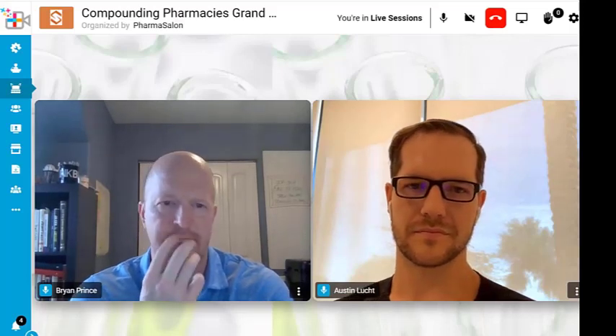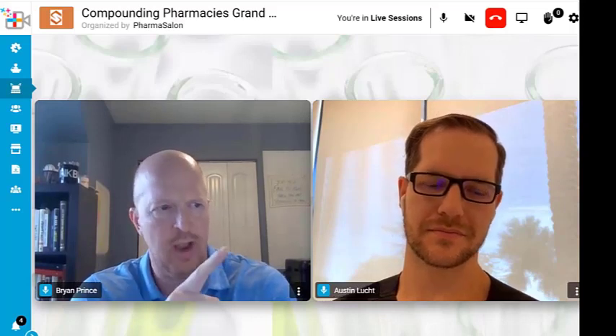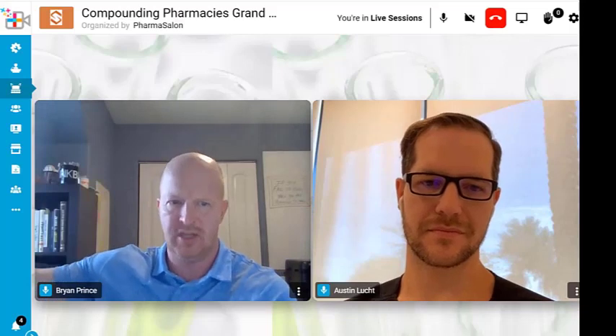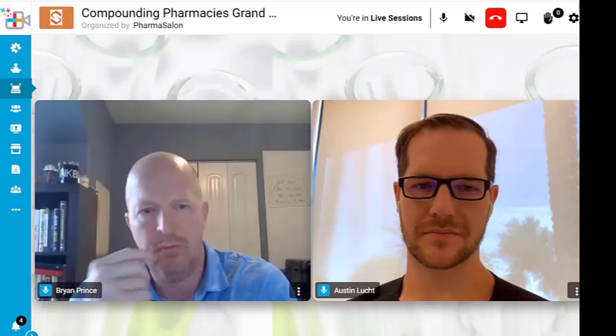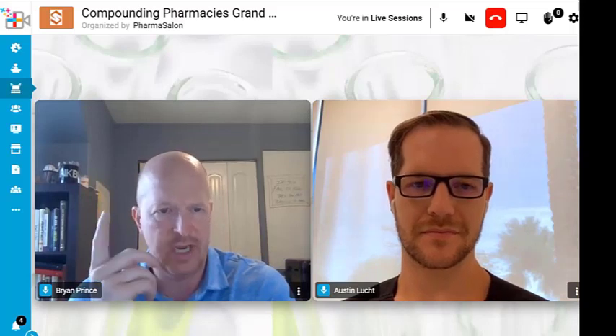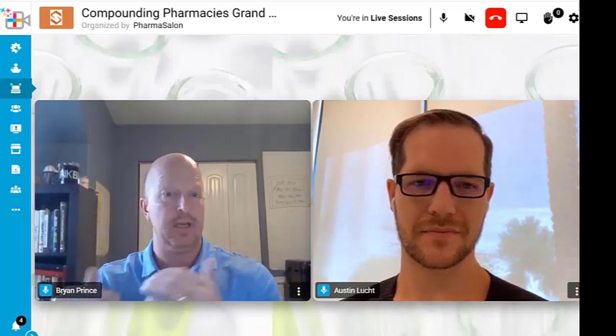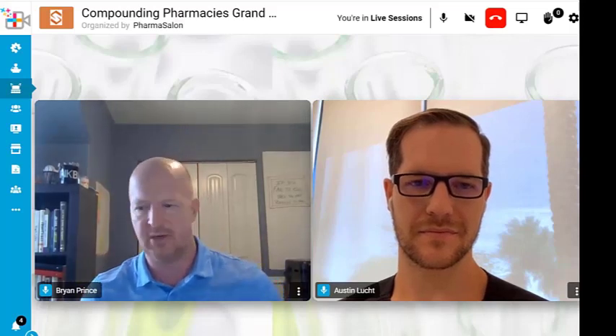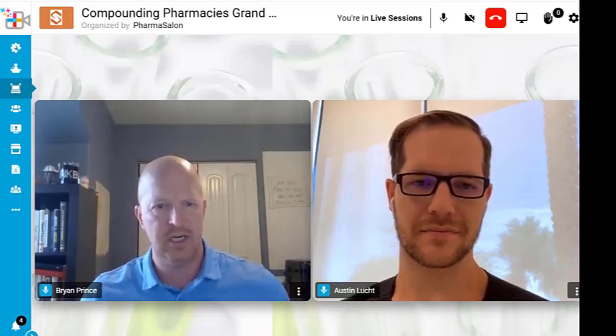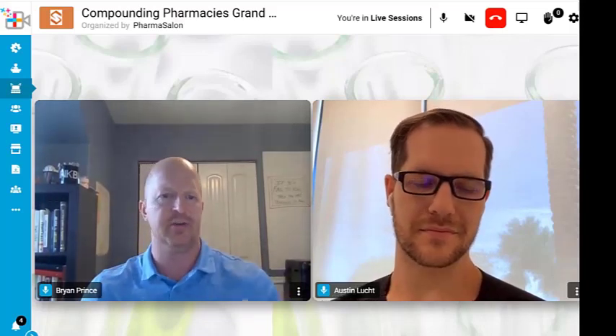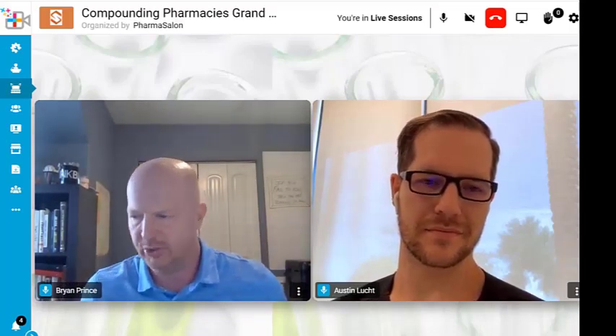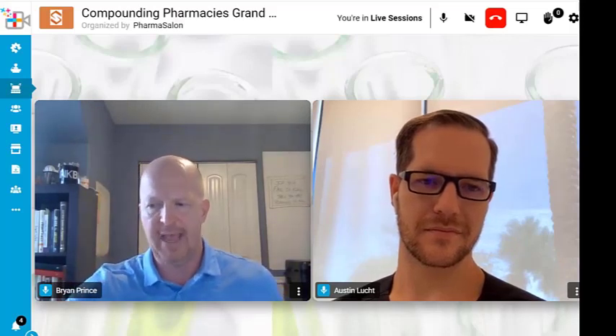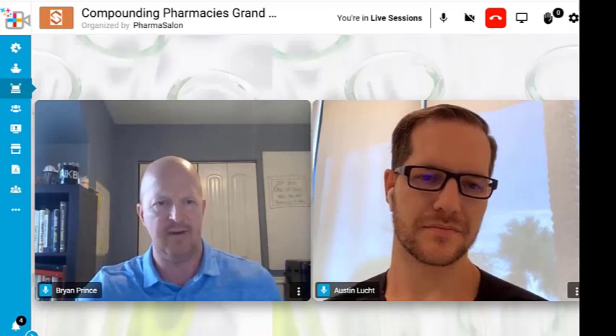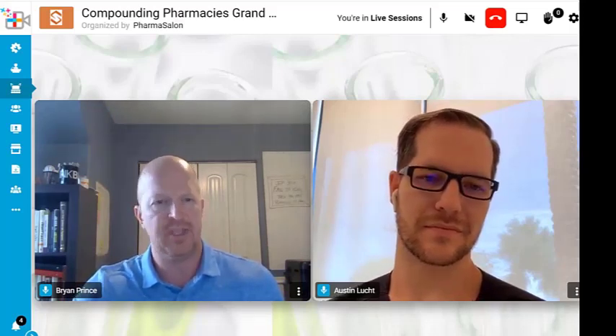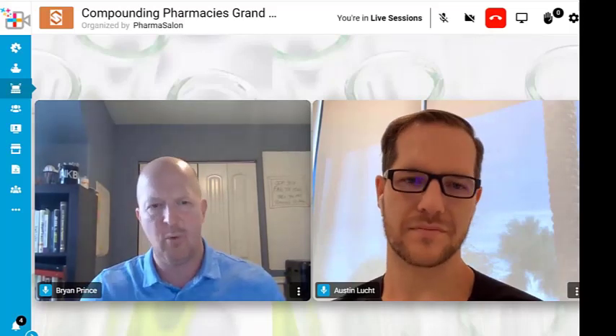That was a stellar question. I tell you, that's the call, as we're waiting for another question to come in, the call that I'll get mostly starting around April, May, June, July, August, September. And I'll get this call a couple times a month at least. And they're saying, hey, we can't control typically the humidity within our clean room. What's the problem? And I'll say, well, that's actually an easy one, because that means the engineer, and I'll have them send me the spec sheets and or what we call cut sheets or product submittal sheets. And sure enough, the engineer spec'd it out at 68, maybe 67, and 60% relative humidity because they were going by USP standards.